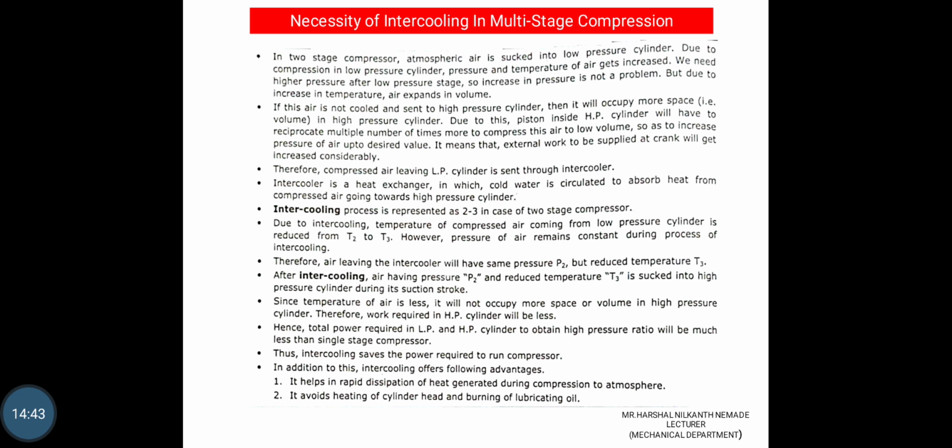If this air is not cooled and is sent to the high pressure cylinder, it will occupy more volume there. The piston inside the high pressure cylinder will then have to reciprocate many more times to compress this air to a low volume, up to the desired pressure. It means that the external work supplied at the crank will increase considerably.